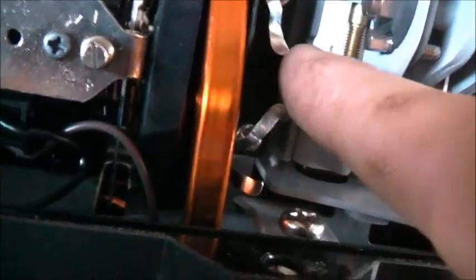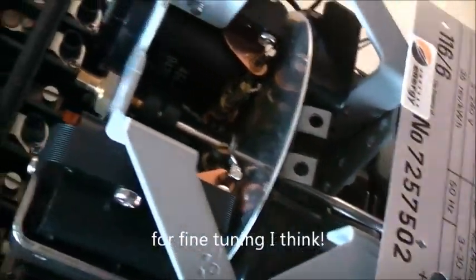This looks like it only has one set. These things here look like they've been cut — they're like shims. I think they're shims used to pack the assembly together with the current coils and get this thing precise. And there are the brackets which hold part of the chassis and everything together, and the potential coils together.